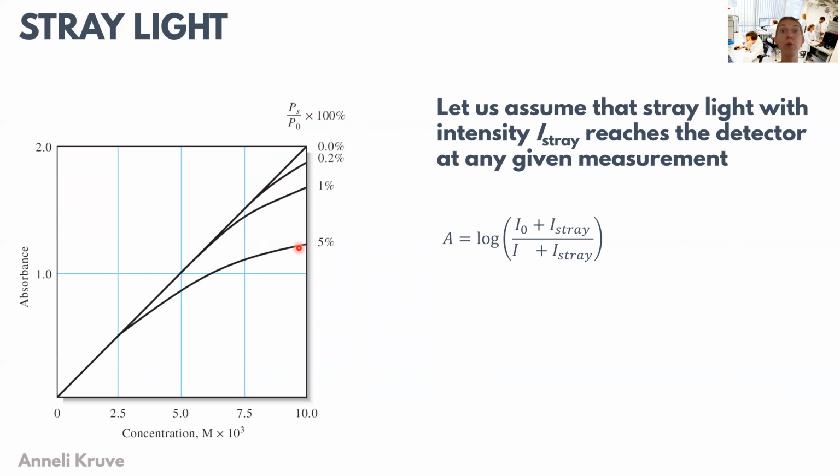An additional important factor with closing the covers is that also during the times when you are not actually doing measurements, the cover should be closed to avoid any light that is coming from the environment to hit the detector.